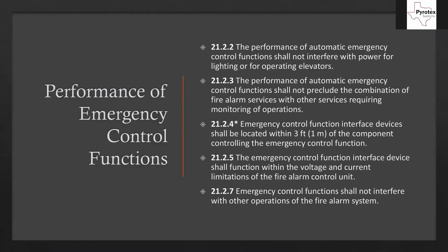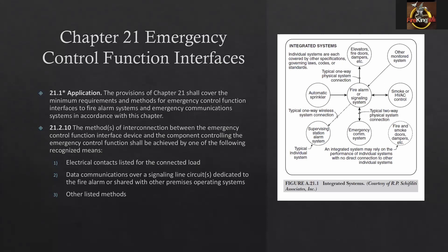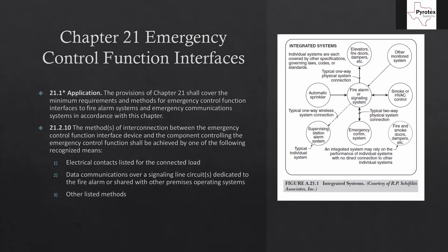Question from student: would sending an override signal to shut off speakers be an example of one of those interconnection methods? Yes, that would be the electrical contacts method — we close or open a switch that the intercom is looking at for an input, and whenever we close or open that switch, they turn their signal off regardless of what's going on, because the fire alarm always has to override whatever other message is being played. Chapter 21 covers any way that the fire alarm connects to any other system in the building.